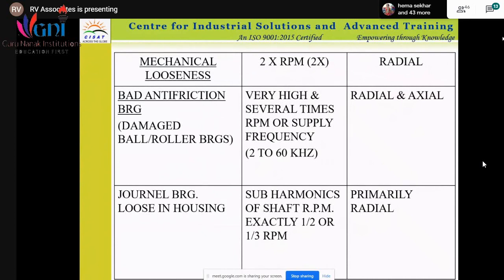Then another is the selection of the bearing. Proper selection should be there for the bearing. The original manufacturer will supply the motor, but in case of failure, if that bearing is not available, then normally people try to get a substitute for that particular bearing. Again, it has to go to the purchase department, who will ask who is cheaper, so they bring the cheaper one. It will not run well because it is not what is suggested by the OEM. So that is a bad anti-friction bearing.